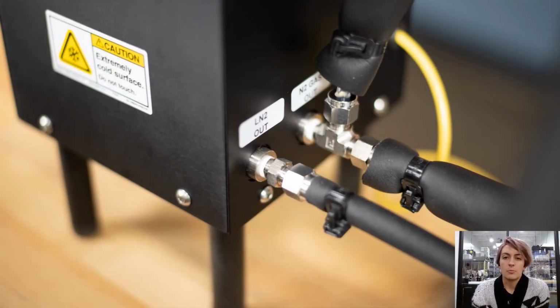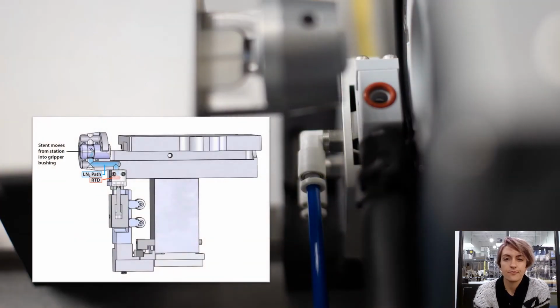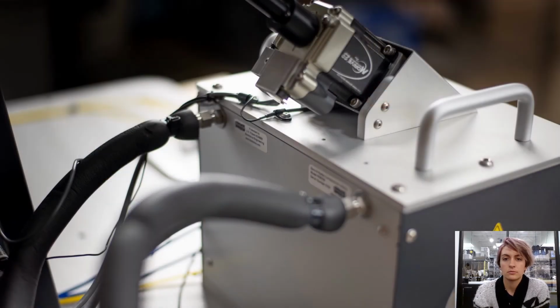During a cooling step, the liquid nitrogen will flow from your source through the phase separator inside of the cooling box. The liquid line will then be directed to the front of the station, where it will flow directly on the stent just before it enters the catheter. The gas lines will then be directed to the back of the station, where they promote a dry environment and help to reduce condensation.